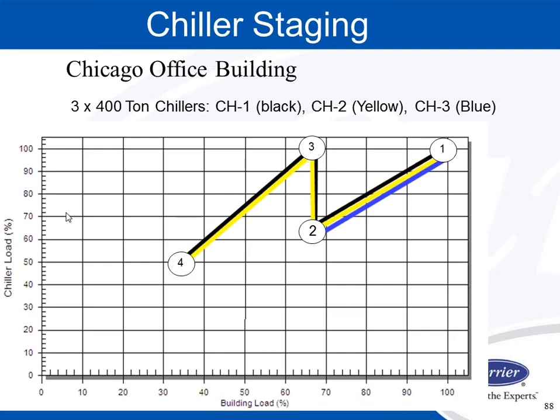My guess, probably never. So we have the 3 chillers that run down to point 2. At the 66% load point, we lose a machine, and then we go to point 3, and then we operate down to 2 machines, down to point 4, then we go to 5, and then we operate with 1 machine from 0 to point 5.